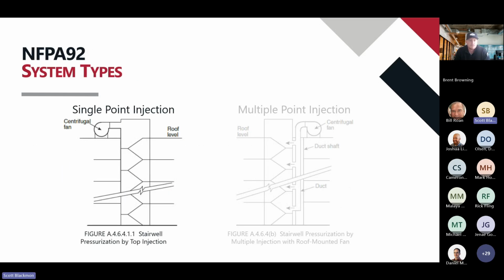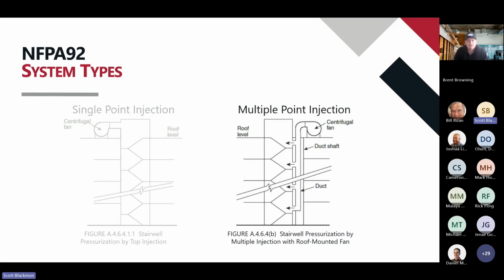So NFPA calls for two system types. They have a single point injection system. Basically, that's exactly what you see there. It's a fan dumping into the stairwell at a single point. NFPA allows this for buildings up to 100 feet. If you go beyond 100 feet, you've got to do a CONTAM study to make sure that it's going to work and work properly.